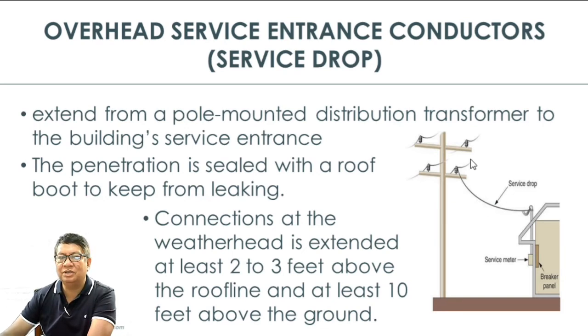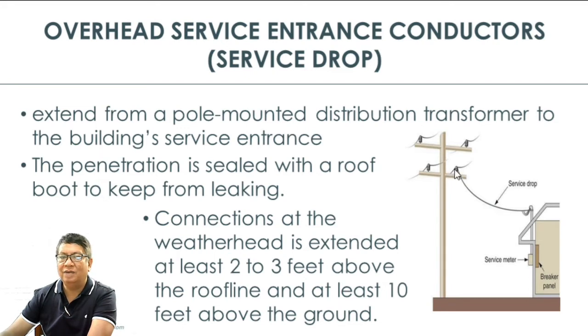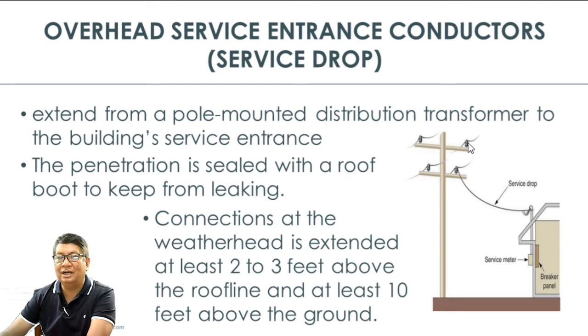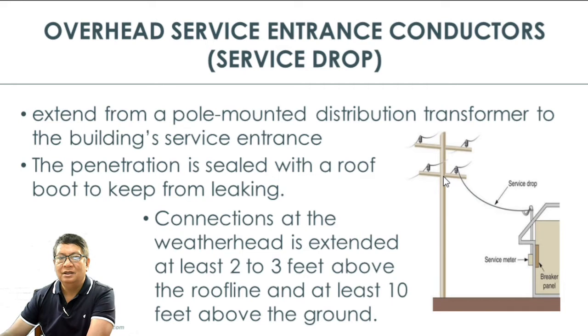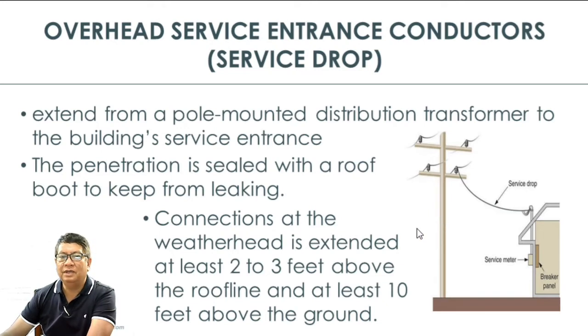The conductors below are the secondary, which have already passed through the distribution transformer. The lines at the top of the pole carry the primary lines at 13,800 volts, while below it is already 220–230 volts — the secondary. The penetration is sealed to keep out leaking. The connection at the weather head is extended at least 2 to 3 feet above the roof line and at least 10 feet above the ground.